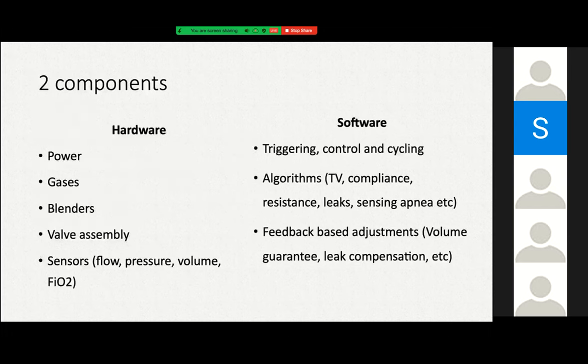Basically any ventilator has two components: the hardware part and the software part. The hardware part includes power, gases, the blenders which mix the gases, the valve assemblies which regulate the pressures, and the sensors which sense the flow, pressure, volume, and FiO2.